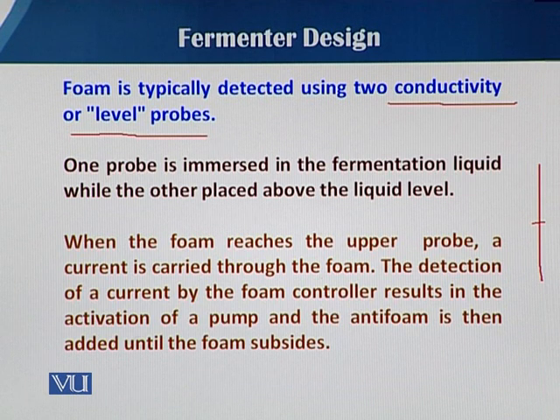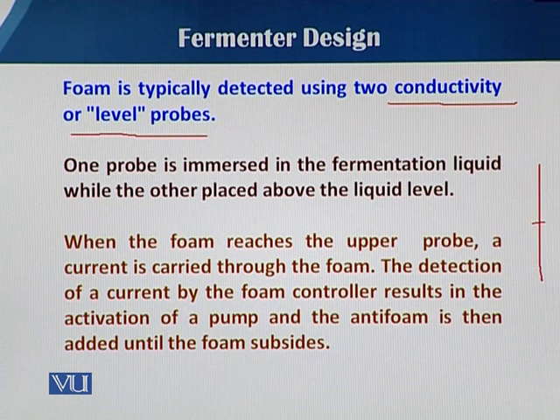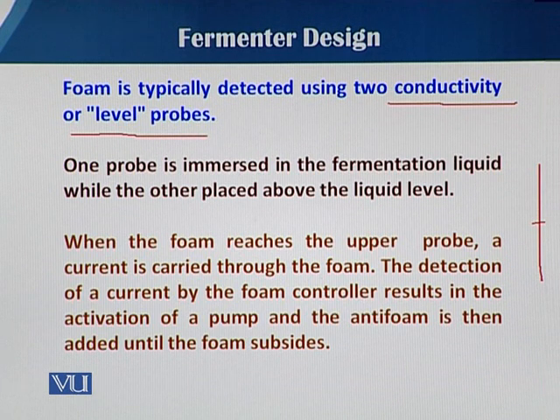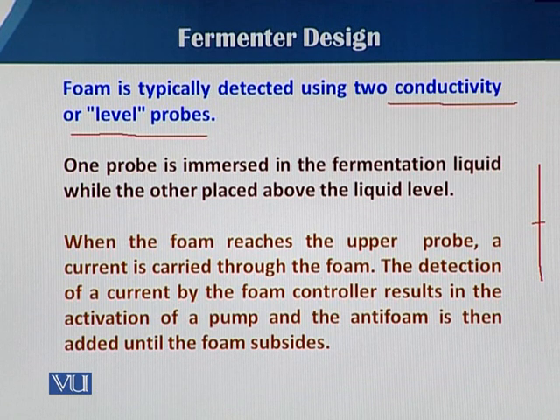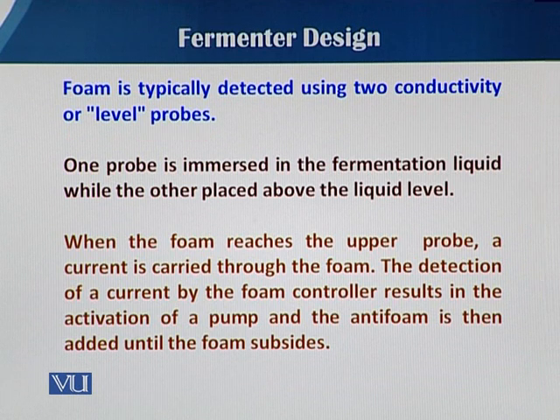When foam reaches the upper probe, a current is carried through the foam. When foam is produced and touches the upper level probe, it sends a signal that turns the pump on, resulting in the addition of the anti-foam agent.